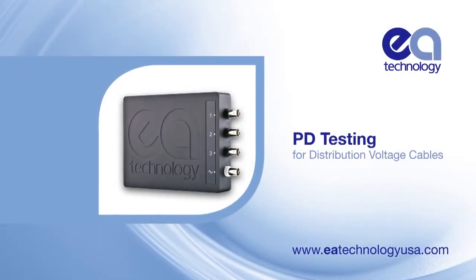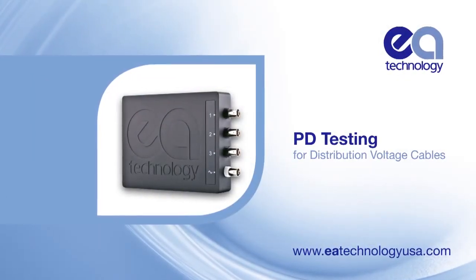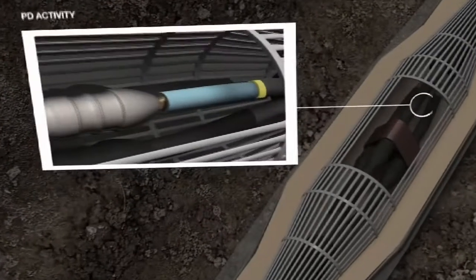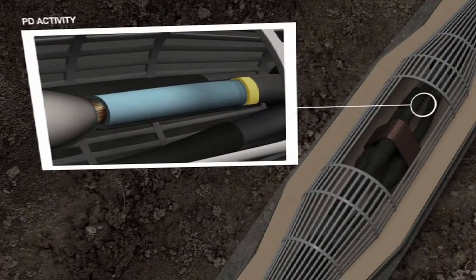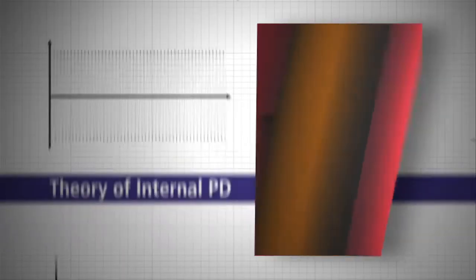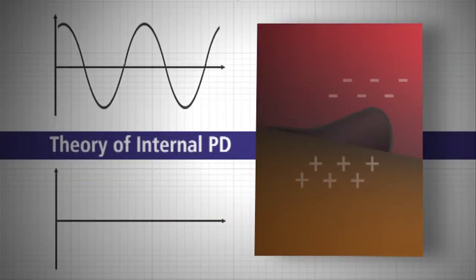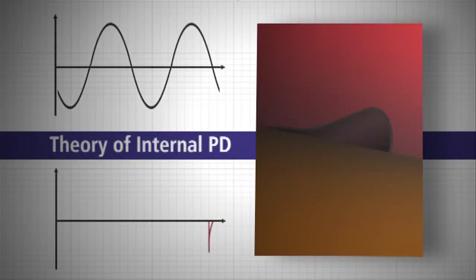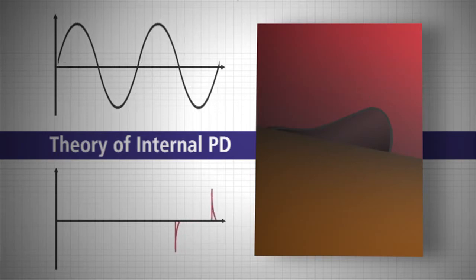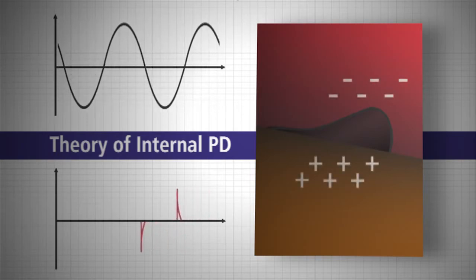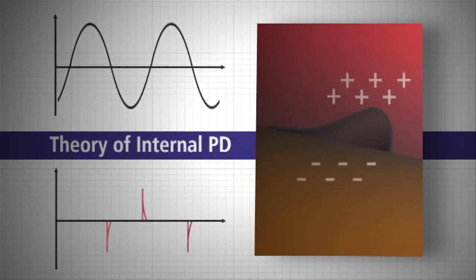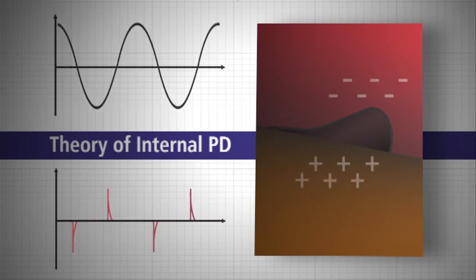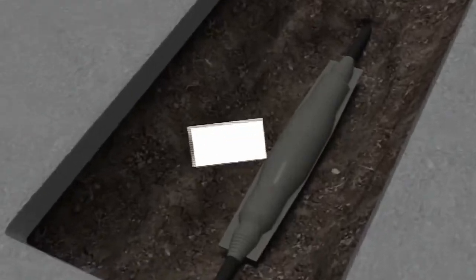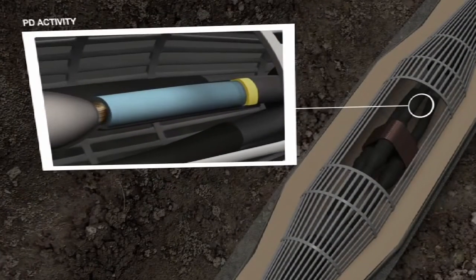PD testing for distribution voltage cables. The presence of partial discharge activity in cables of all kinds gives a clear indication that insulation is starting to break down. The cause can be anything from manufacturing or installation faults to accidental mechanical damage. But one thing is certain: if PD in cables remains undetected, it will almost certainly get worse, and that can lead to sudden failure and outages.